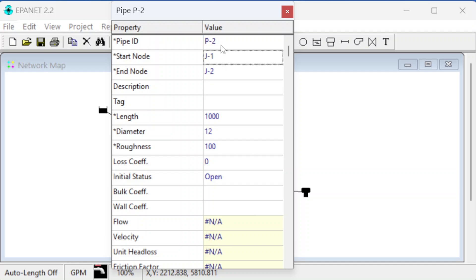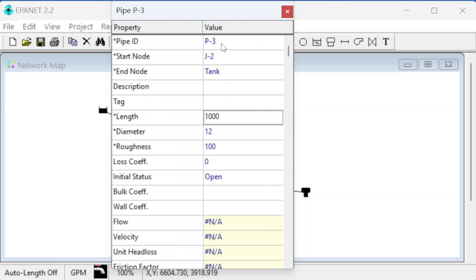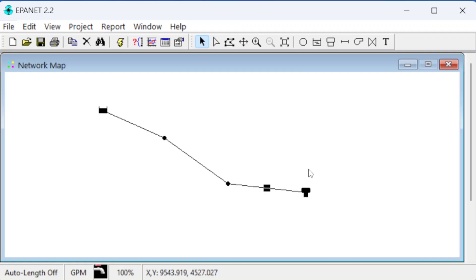Pipe P2 goes from J1 to J2. Note that if flow goes from J1 to J2 it will be positive; if reversed, it will be negative. Make sure you draw the pipe in the expected flow direction so flows show as positive. P2 has a length of 200, a 6-inch diameter, and a roughness of 100. Then the last pipe, P3, has a length of 300, a 6-inch diameter, and roughness of 100.